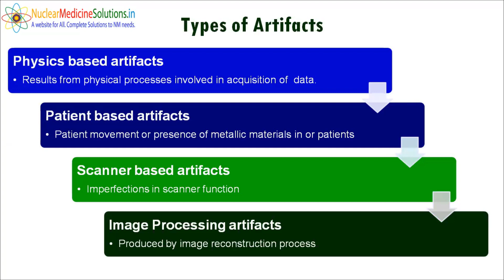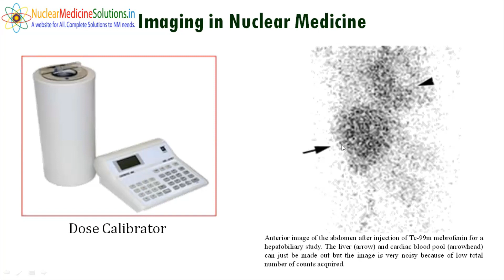So before administering the activity to the patient, we measure the activity by using the dose calibrator. And if your dose calibrator is not working properly, then it can underestimate or overestimate the dose. This is an example where, because of malfunctioning of the dose calibrator, the dose was overestimated. Because of that, we injected less activity than the desired activity in the patient. And because of that, we are getting an image which has a lot of noise in the image.